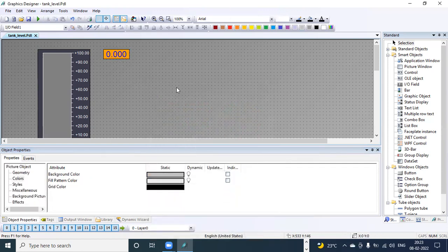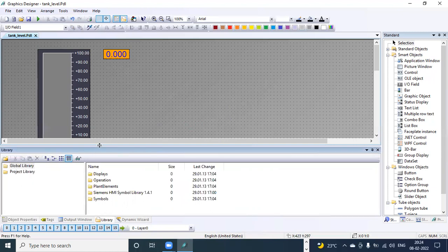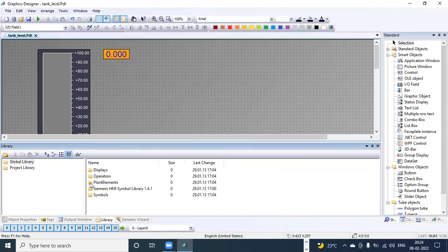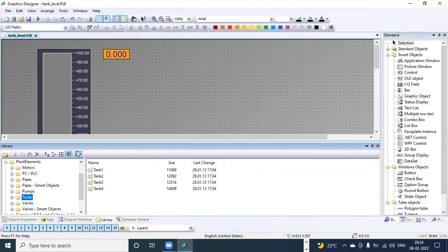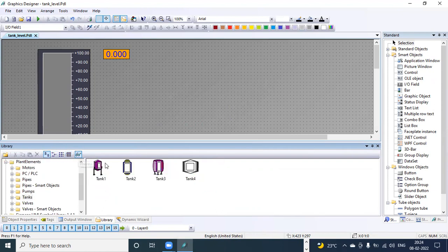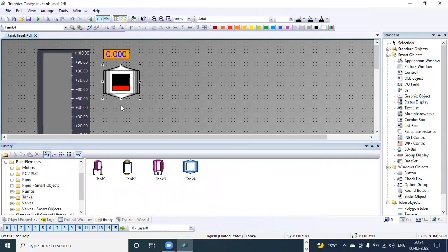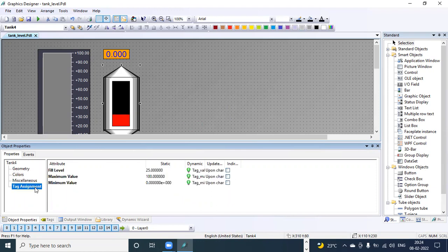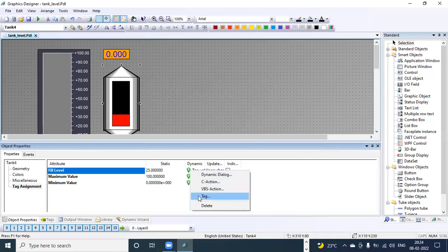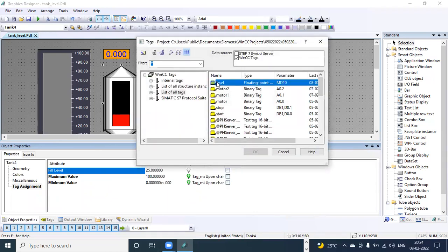There is one more option in the Library. In the library we have Plant Elements — in the last class we looked at motors, today we will see tanks. In the tanks section there are different types of tanks. Select one and drag it in. In object properties for this tank, go to tag assignment, then fill level. Right-click for dynamic and select direct tag — assign "level".